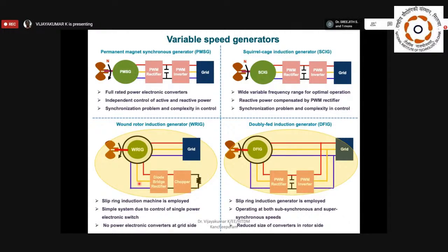You can say 3 to 5%. For a higher rating machine, it's 2 to 3%. So only the slip power is recovered here, and that's why the converter ratings are lower compared to the top two topologies. Now we'll discuss the wound rotor induction generators.